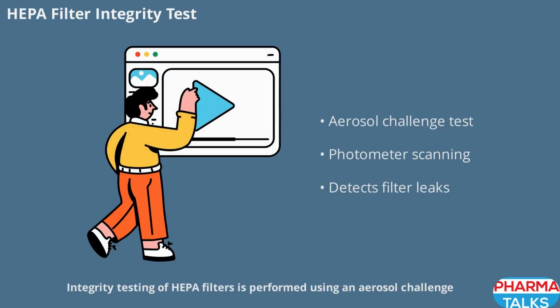Integrity testing of HEPA filters is performed using an aerosol challenge, typically with PAO or DOP aerosol. A photometer scans the filter face to detect any leaks or failures. This test is critical for ensuring that the filter is functioning properly and that no contaminants are bypassing the filtration system. Regular integrity testing is a key part of maintaining cleanroom standards.